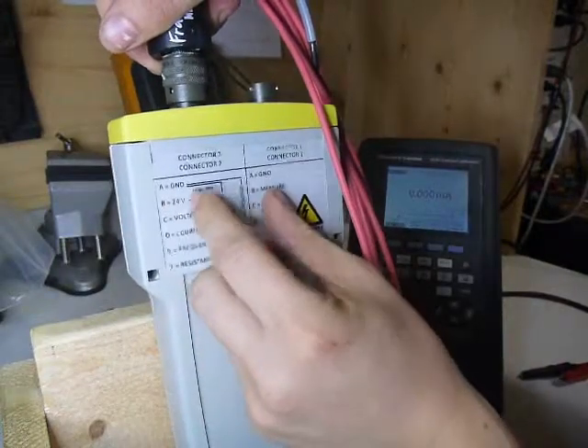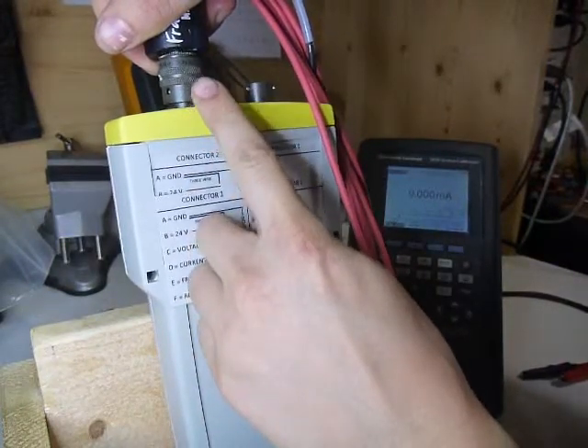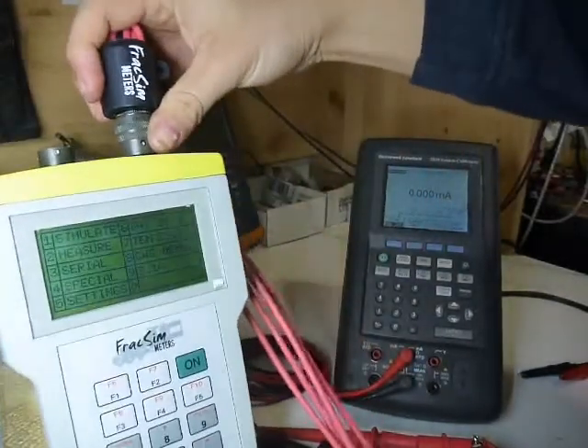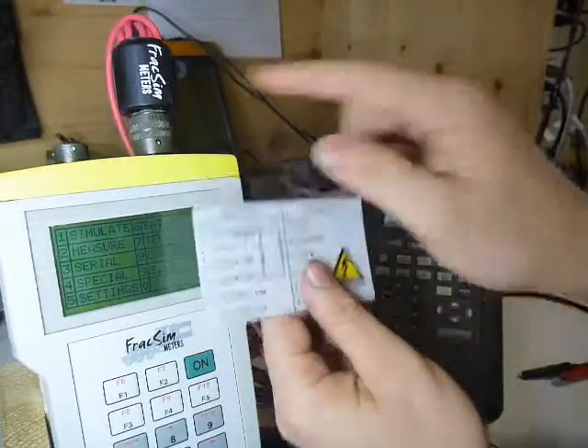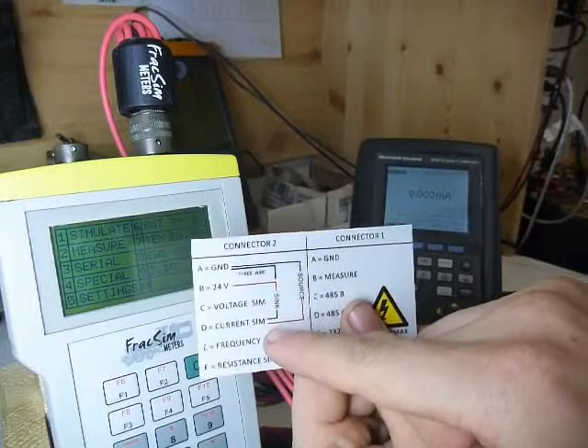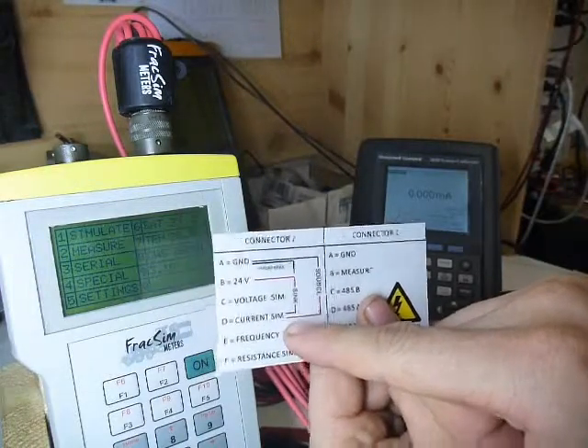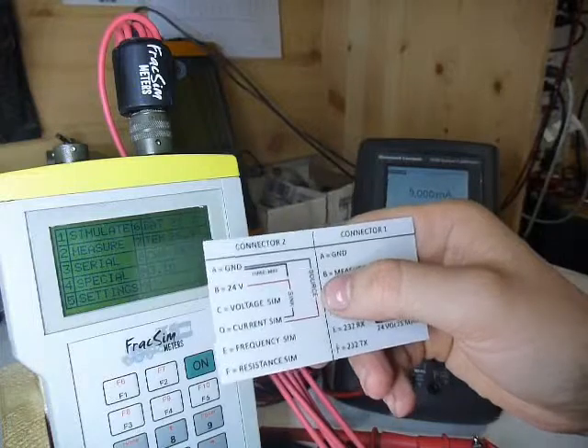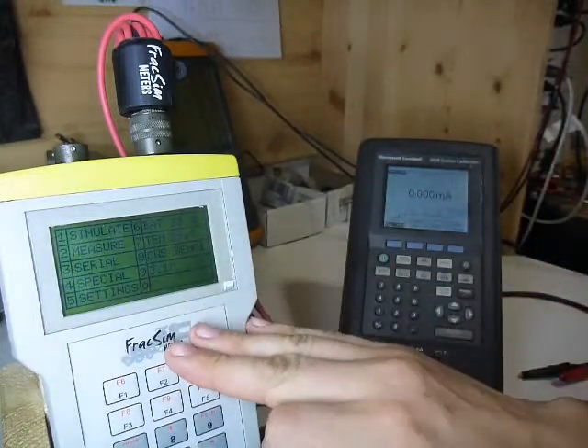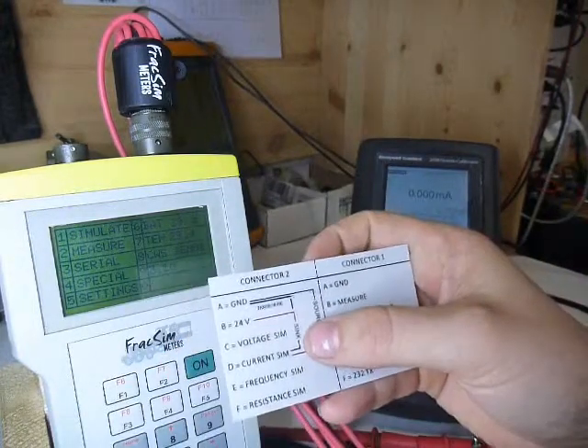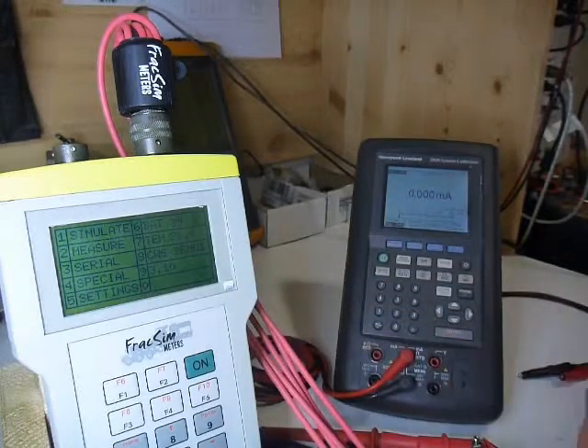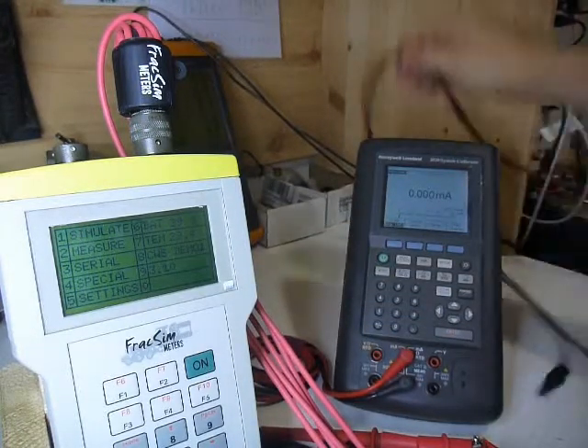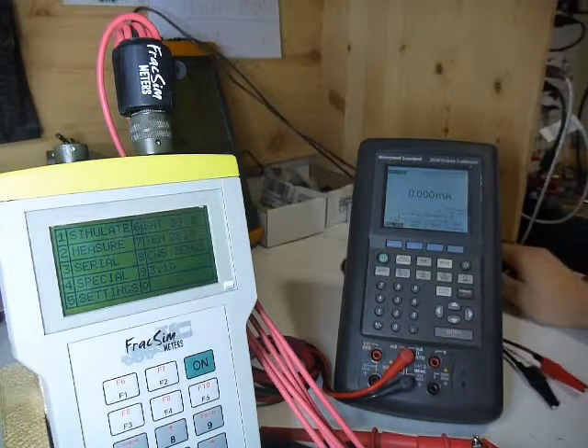It lines up where it says what's on this side lines up with that connector there. So I'll be using that for demonstration, but basically that connector shows you all the correct connections for sinking and sourcing current. Sourcing current is, of course, when you use 24 volts from the meter to drive the current, and sinking is when you use 24 volts from an external source. And I have a bench power supply we're going to be using for that.